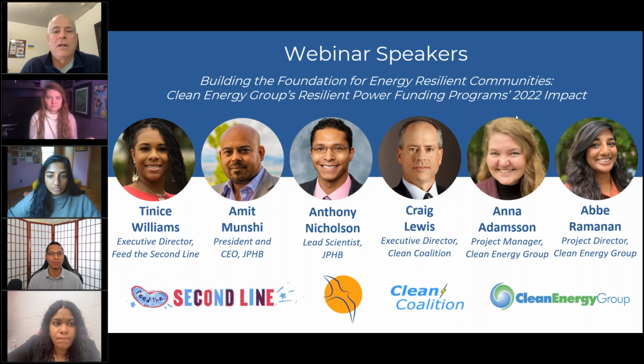So the inverters capable of grid forming and black start are a little more expensive. All in all, I'd say the premium required to go from a simple solar and storage deployment that turns off if the grid goes down, compared to a solar microgrid designed to stay up when the grid goes down, is about 10%. So you're adding about 10% to the overall cost of the project.